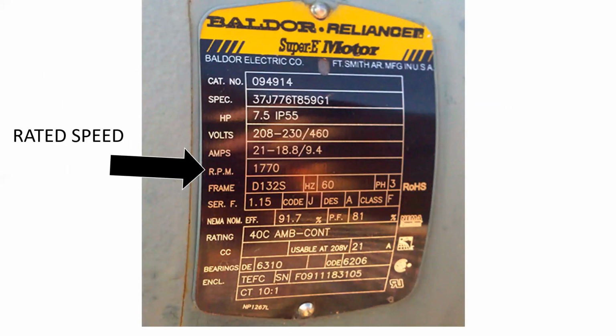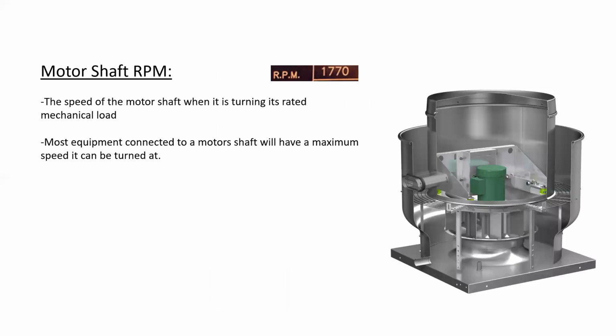Rated speed. This motor has an RPM of 1770. The motor shaft RPM is the speed of the motor shaft when it is turning its rated mechanical load. Now, most equipment connected to a motor shaft will have a maximum speed that it can be turned at, or what it's rated for. Case in point is this restaurant ventilation fan that's usually situated above the grill in a commercial or restaurant kitchen. The motor is in the center. It connects to a large ventilation fan wheel, and that sucks the air up and out around the sides of this unit.